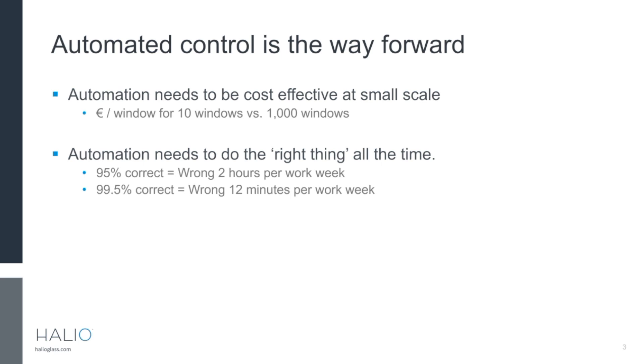The other thing is that automation needs to do the right thing pretty much all the time. If we aim for a 95% correct rate — which is a pretty high bar — we're still wrong for two hours of the work week. And occupants vividly remember the time the shading system is not doing the right thing. So we need to get closer to 99.5, maybe 99.8 or 99.9%, in the view of the occupants so that they'll be satisfied.